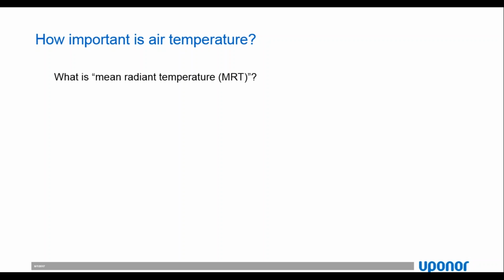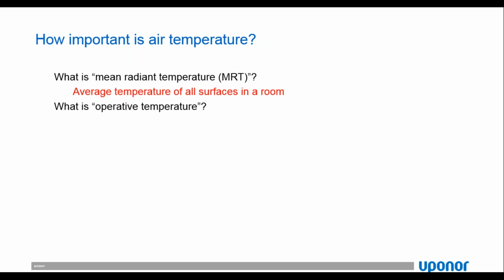Now, there are thermostats today that can measure mean radiant temperature in a room, and what they do is take the mean radiant temperature, add it to the air temperature, divide it by 2, and you get something called operative temperature, which is the true measurement of what you're feeling for temperature inside of a room.